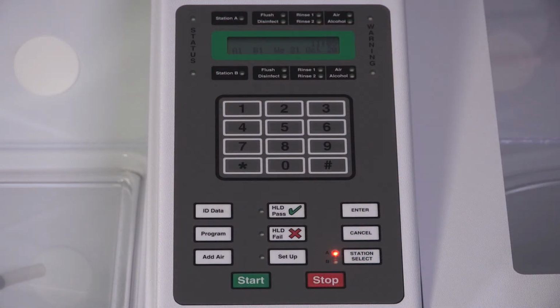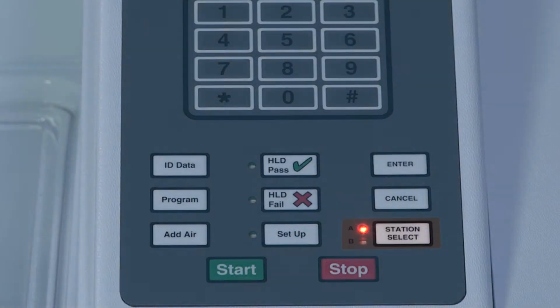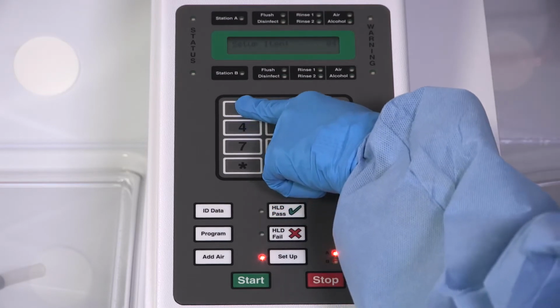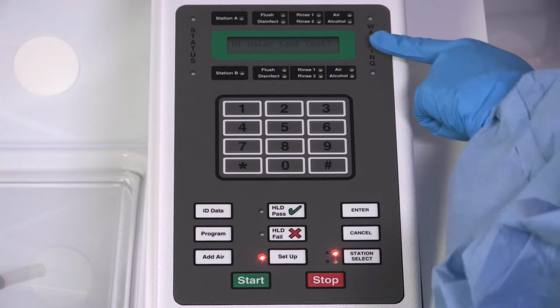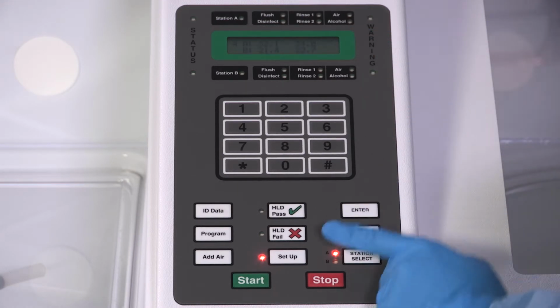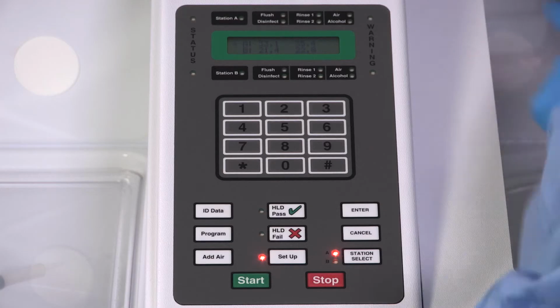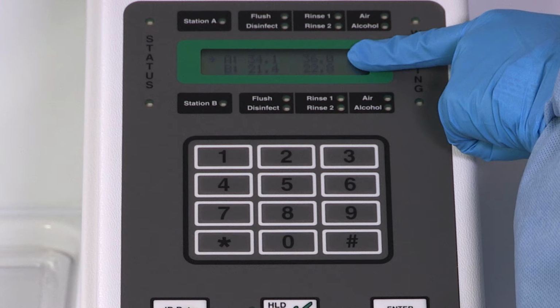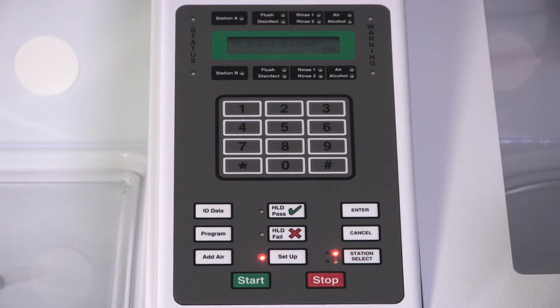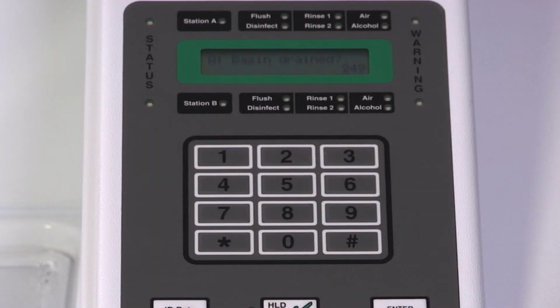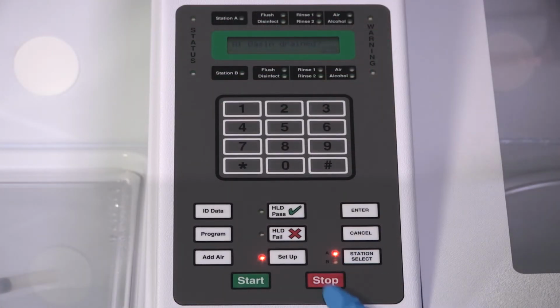You can also confirm the water temperature by using a setup function. First, use the Station Select button to illuminate the desired station and install a basin restrictor. Then, press Setup, 41, and Enter on the control panel. The display prompts Water Temp Test. Press Enter to initiate water flow into the basin. As water is flowing, verify the incoming water temperature reading on the display, which is the number on the right for the basin selected. Once the incoming water temperature has stabilized at approximately 35 degrees Celsius, press Stop to stop the inflow of water. The display will show Basin Drained. Once the basin is completely drained, press Stop again to close the drain valve. This concludes the daily startup segment.